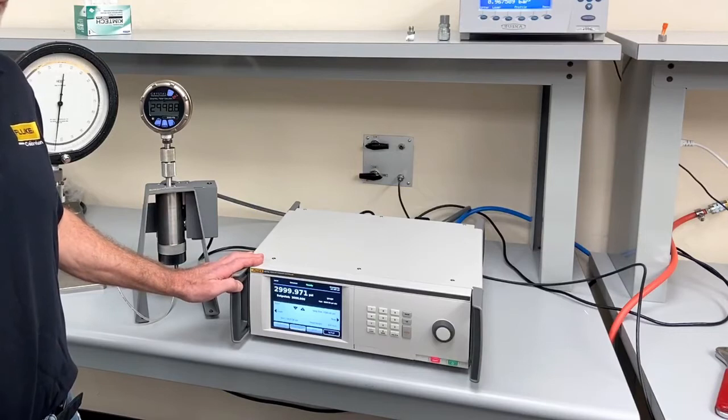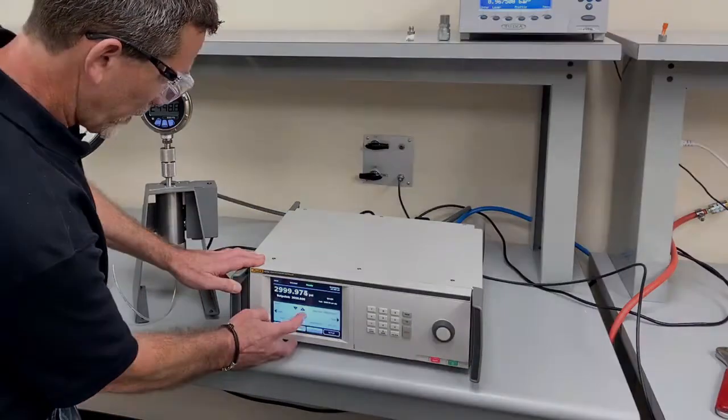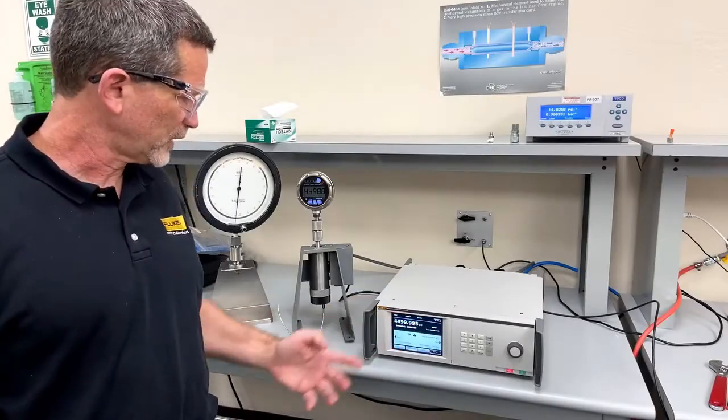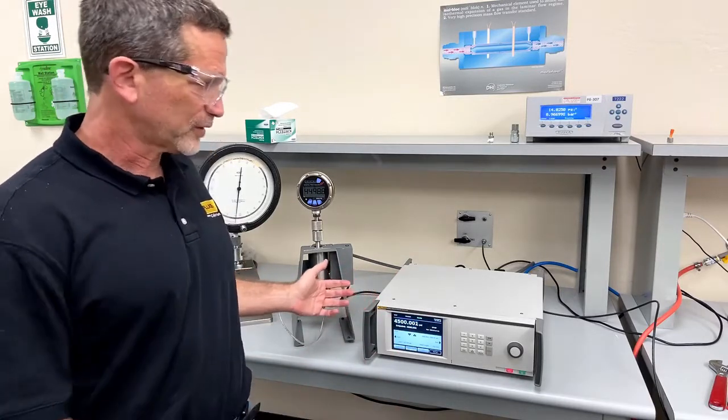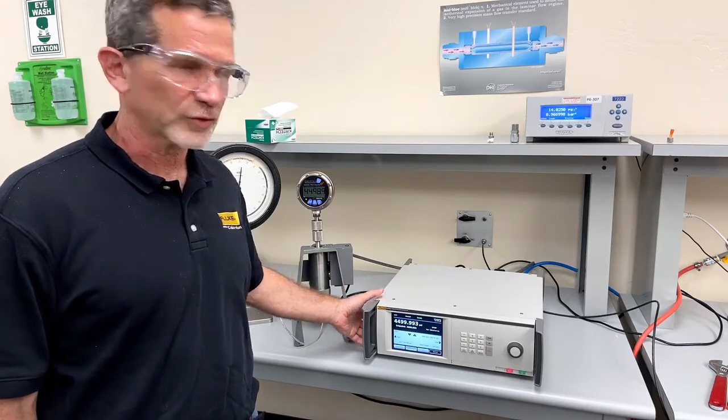Now we want to go to 4,500 PSI. We can simply hit the step button. So we've reached 4,500 PSI. We're controlling very tightly. When the booster is not accelerating, you can hear how quietly the controller controls.